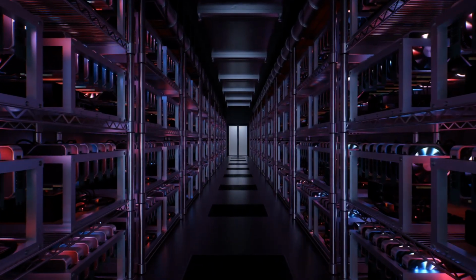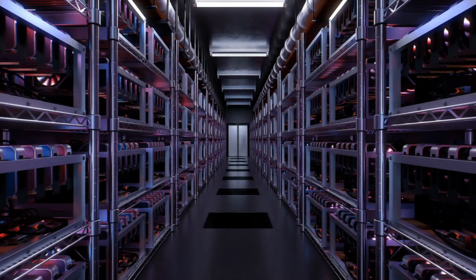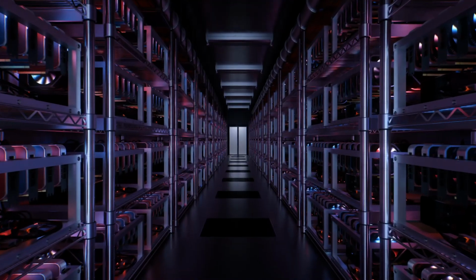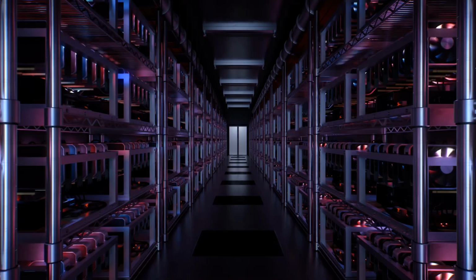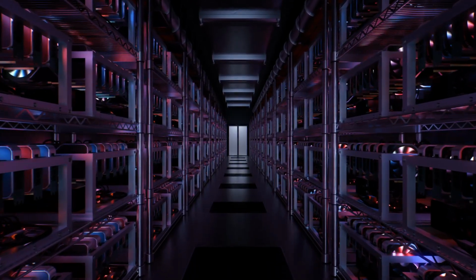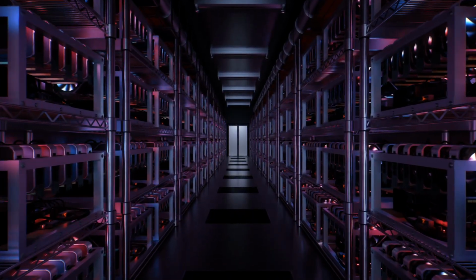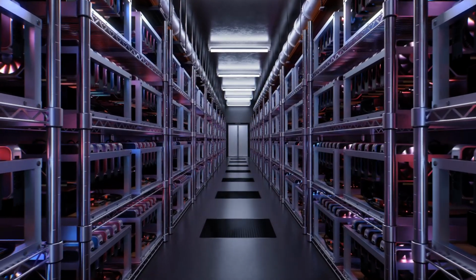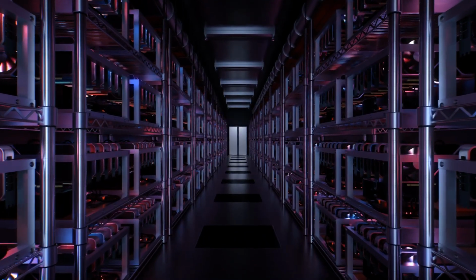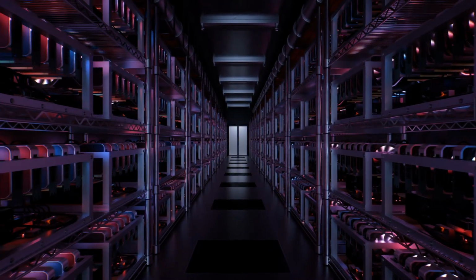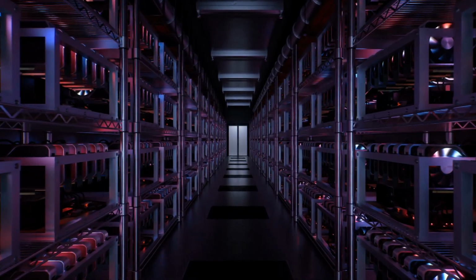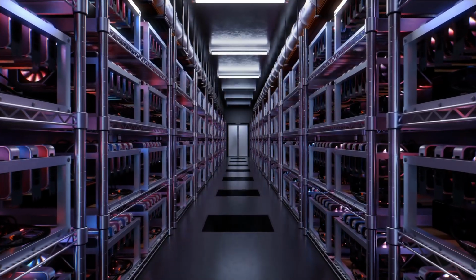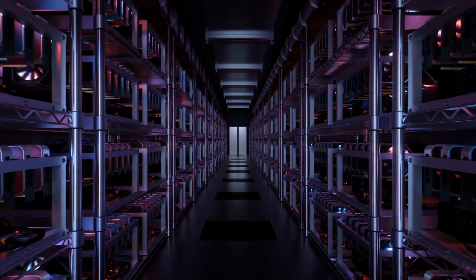So an ideal mathematically perfect PUE would be 1.0, meaning every single watt of power pulled off the local utility grid is going directly into computation, and exactly 0 watts are being wasted on facility overhead. A PUE of 1.0 is the impossible ideal. Historically, older, air-cooled data centers operated with a PUE of 2.0 or sometimes even higher.